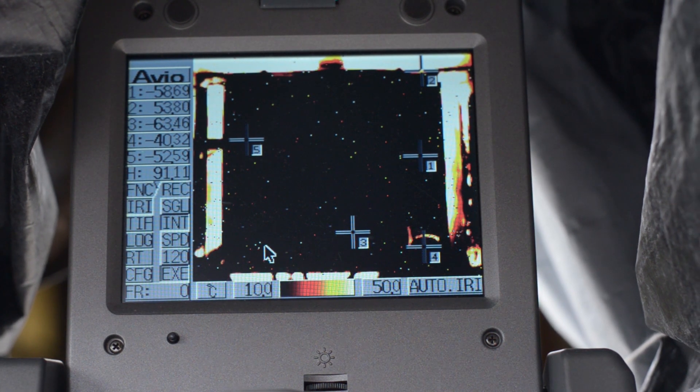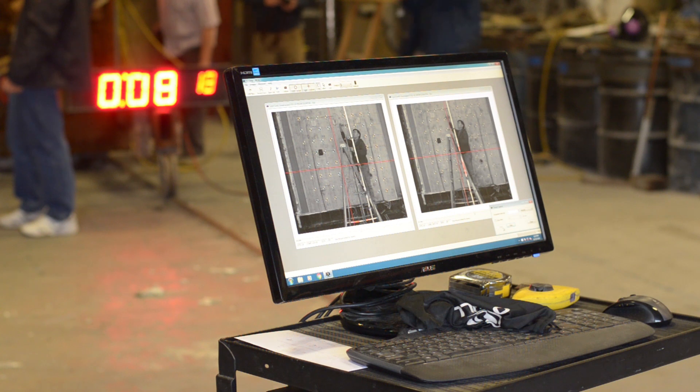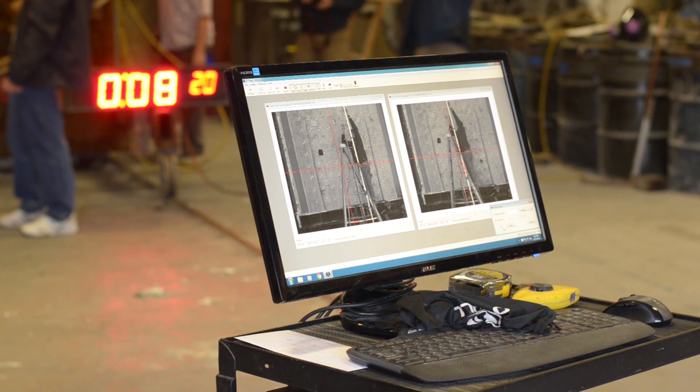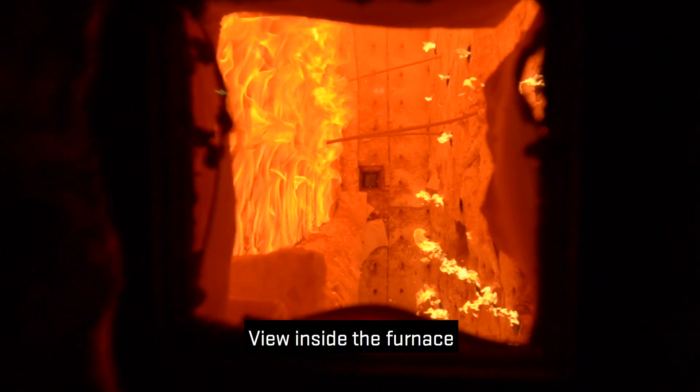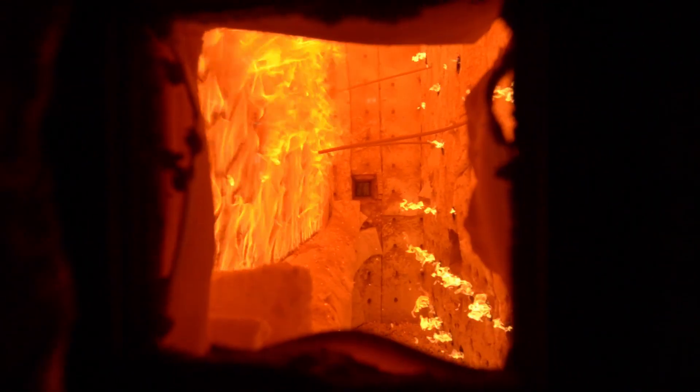The results are generally quite promising. Looking at it through the thermal camera, no suspicious flashes of high temperature, no transmission of high temperature gases until the very last period of the test. Five out of six of the assemblies that we've tested lasted two hours, and could last probably longer. There was nothing indicating any immediate collapse.